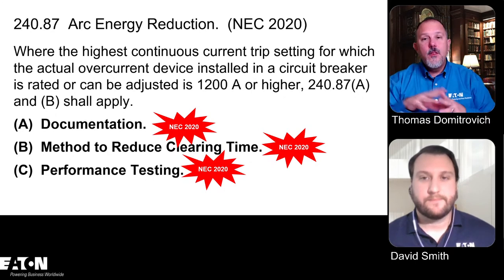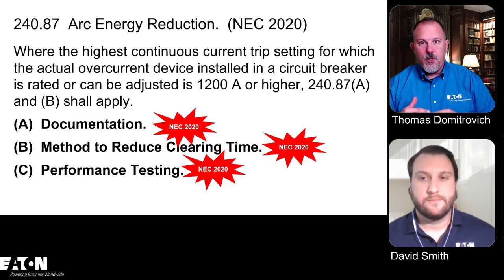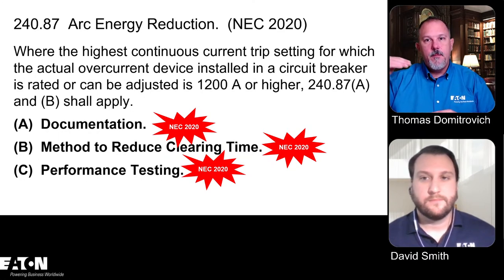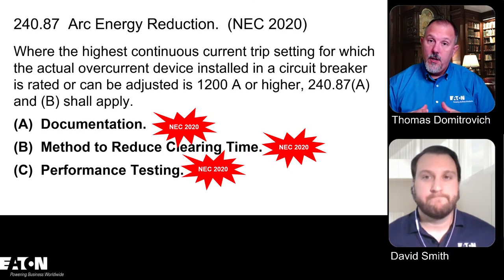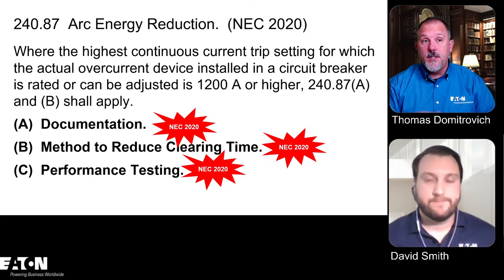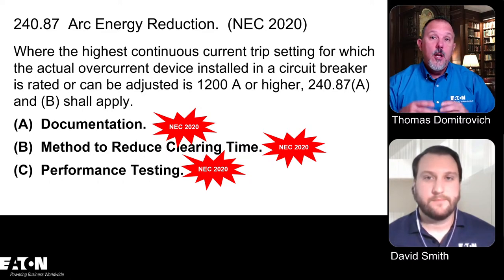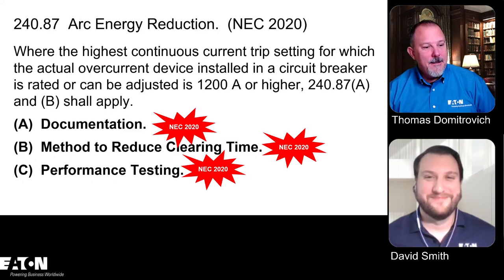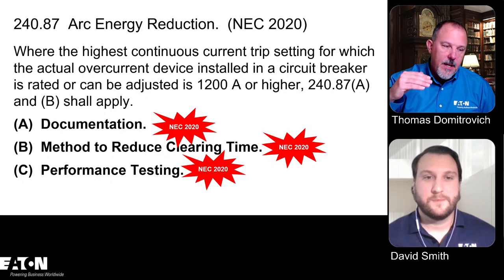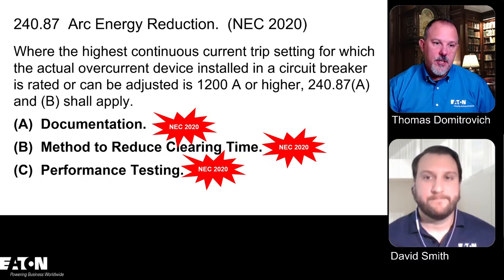Now, in the world of incident energy and arcing currents and clearing time, when my voltage goes down on that secondary, my available fault current goes up, but my arcing currents are pretty low. They're much lower, and that's significant in the 240.67 and 240.87 because on a 208 volt system, my arcing currents are going to be much lower than on a 480 volt system. And even though proportionally, when you think about the bolted fault currents and whatnot, but the analyses that I've done, in the 208 volt systems, it's harder to get that current high enough to be in the instantaneous region.